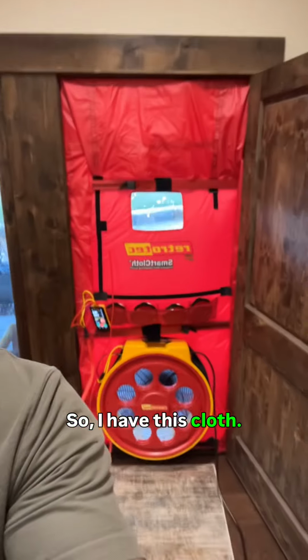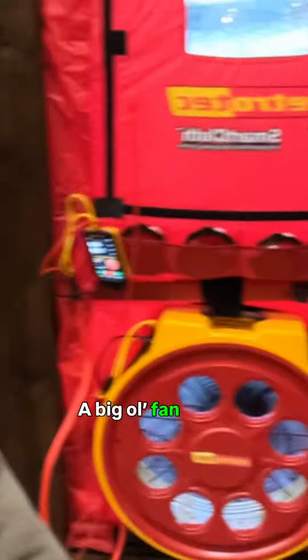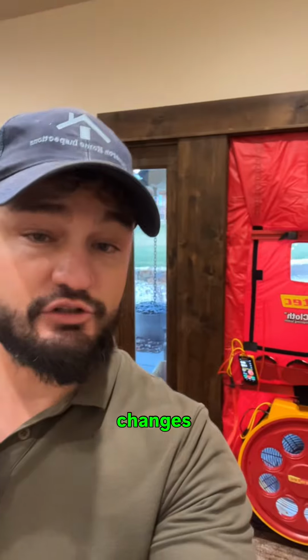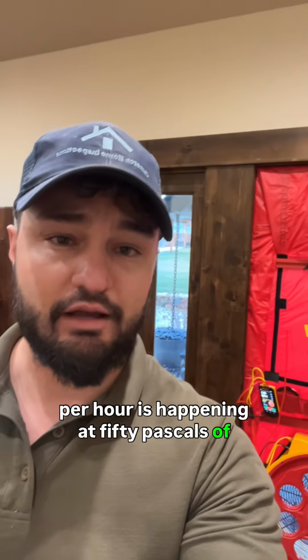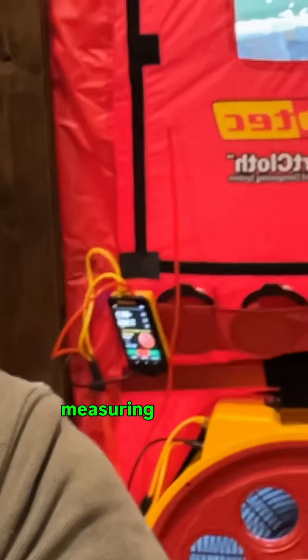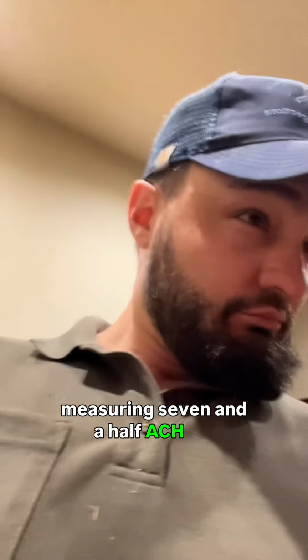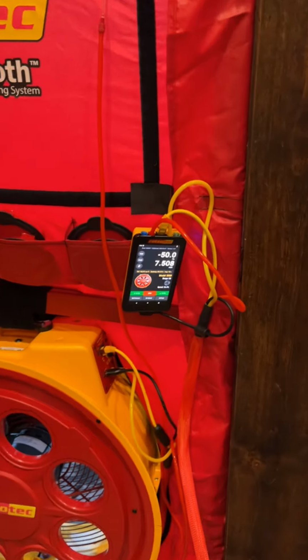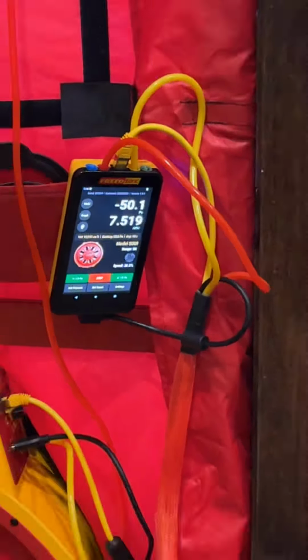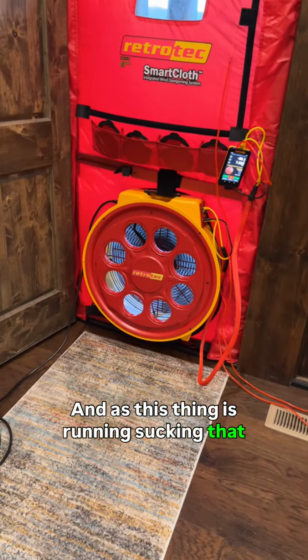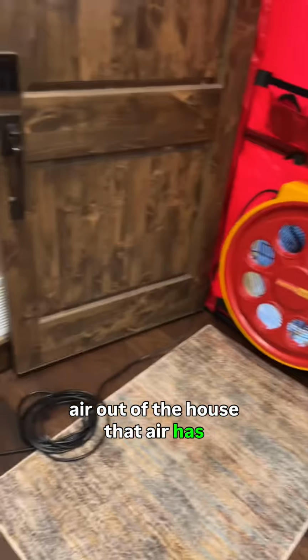So I have this cloth, big old fan, and a digital manometer that is measuring how many air changes per hour is happening at 50 pascals of pressure, ACH 50. Not going to get into the weeds on all of that stuff right now, but we're measuring 7.5 ACH 50, roughly. And as this thing is running, sucking that air out of the house, that air has to be replenished from elsewhere.